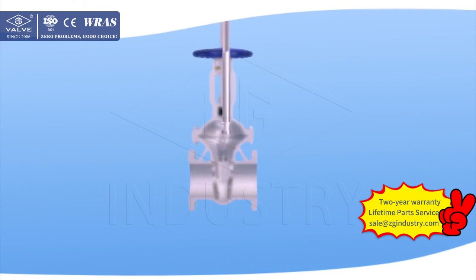3. Adopt rising stem. Stem and disc are connected by a T-shaped groove. The T-head and stem are forged together to guarantee enough connection strength. Flexible disc structure can avoid sticking caused by heat expansion.